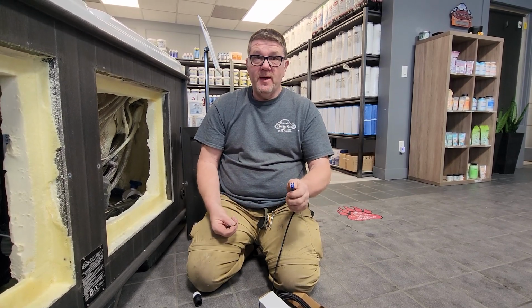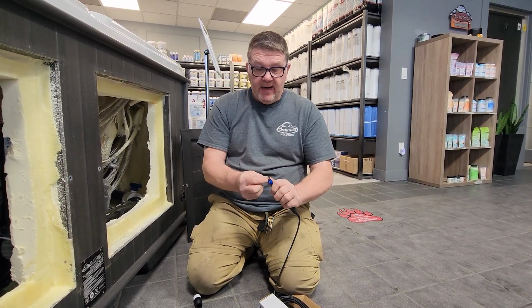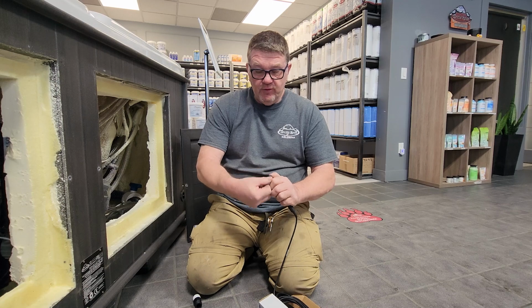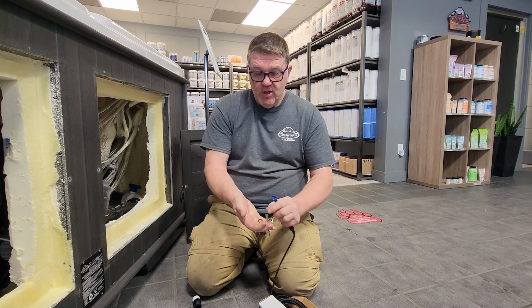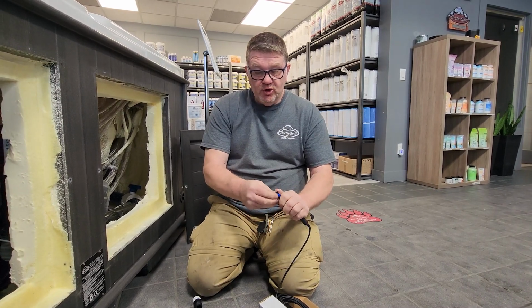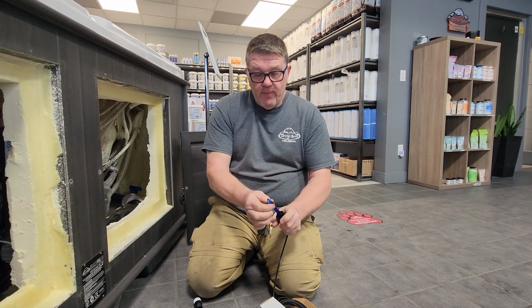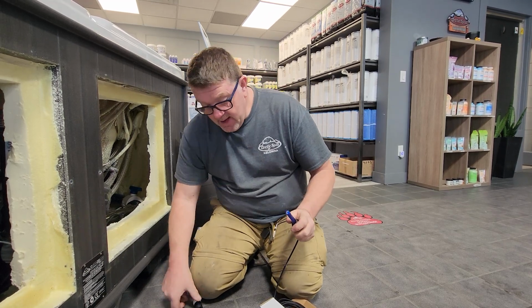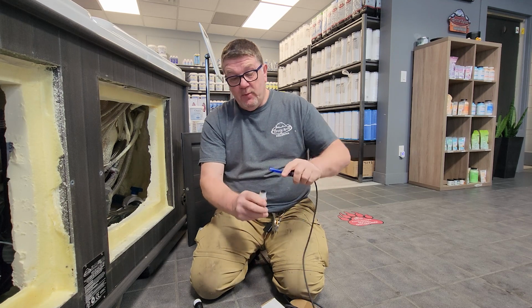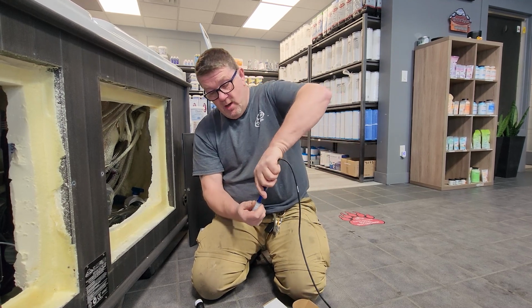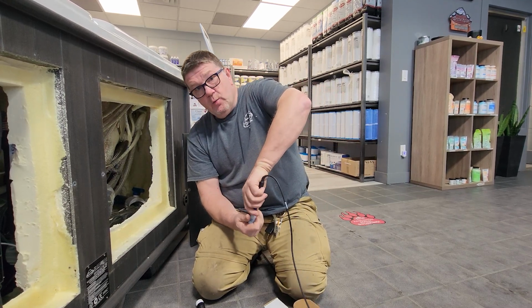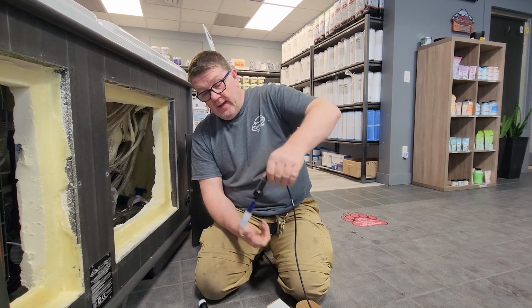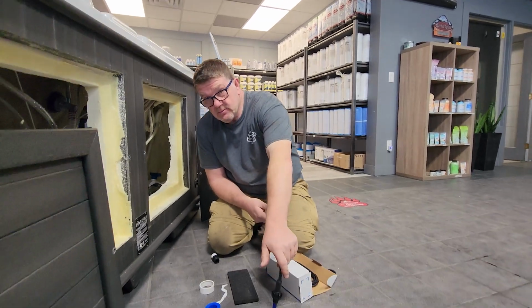The end of the probe has 2 glass balls on it. We have to make sure those glass balls do not get damaged. So first, we put the 2 rubbers over the top, push them all the way down to the bottom, and then for the time being we're just going to put this back into the water. By putting it back into the water, we can hold it in place. We don't need to do anything else.